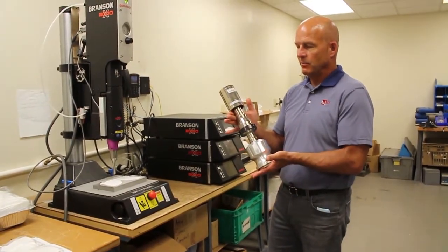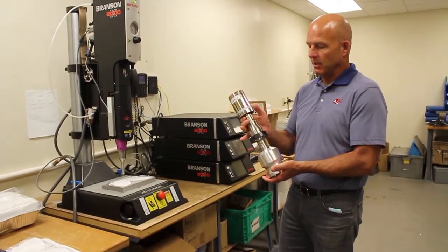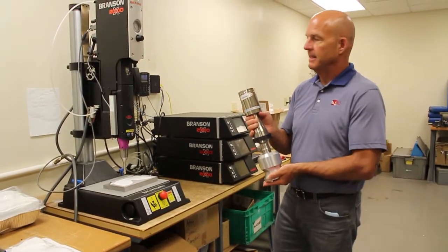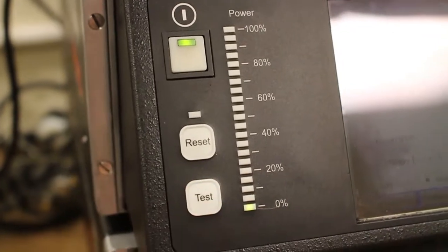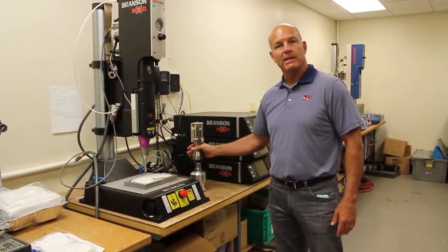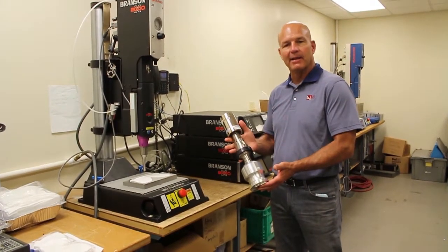So the condition when you get an overload is to take the whole stack assembly apart, replace the studs at the interface, torque things properly, put it back into the system, hit the test button, and if that overload condition goes away, then you found something wrong in the stack component, you put the stack back together, and you're in good shape.